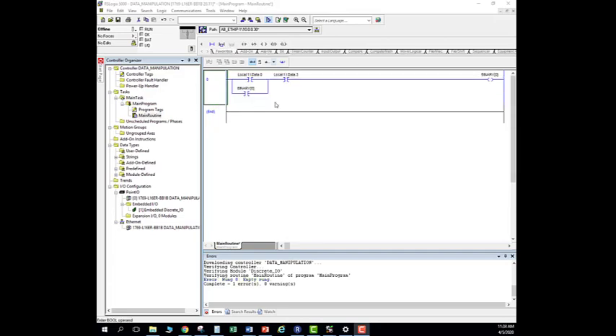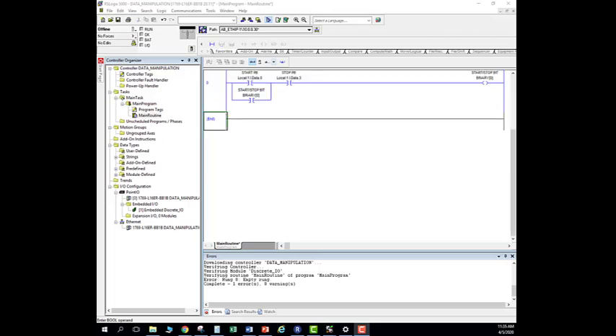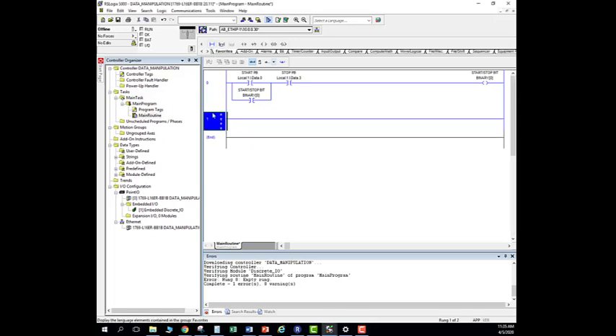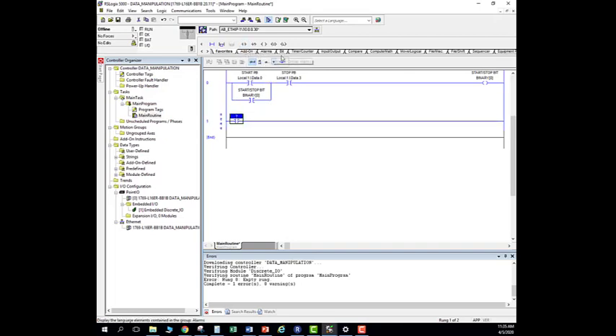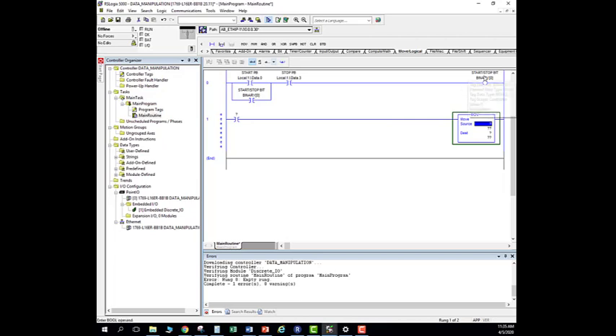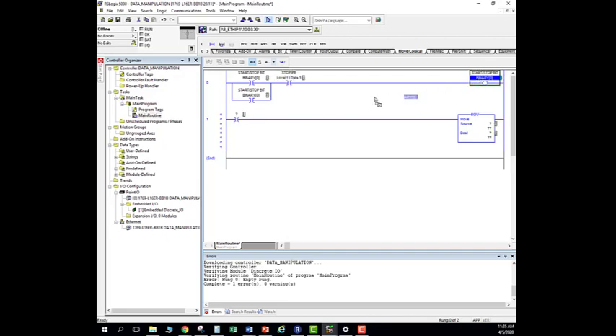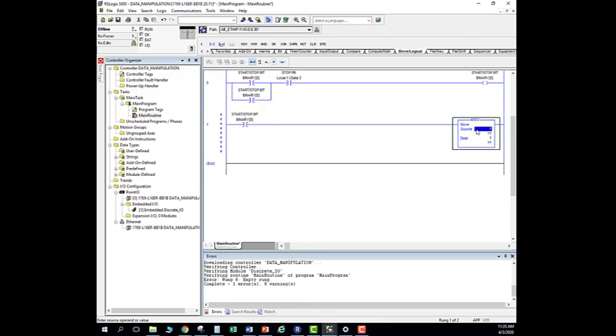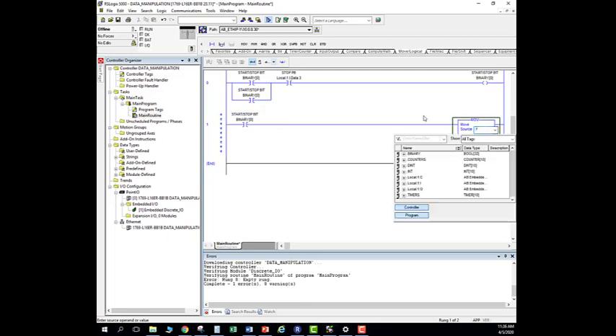As you can see here I've created the sealing logic or start-stop program using an internal binary bit. Next I need to add the move statement. I'll bring you through the whole step process. First thing I want to do is grab a rung, create a new rung. When this bit comes on I drop it in here, and then I want to come over here to the move function. MOV is over here, so I've got the MOV key and I'm going to grab this and drop it in right there.